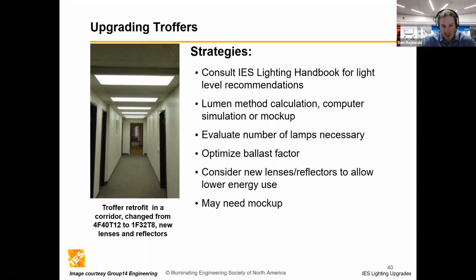You're going to look at your IES manual to figure out the light levels you need, like 300 lux for an office or higher depending on what's going on. You may want to even mock it up to make sure people aren't going to complain that the lights are glary or causing other issues that may not be visible when just looking at a floor plan layout. If using existing fixtures, you may want to look at replacing the lenses if they're damaged, dirty, or miscolored because of sun or time. So that's kind of the basics you look at when upgrading troffers.